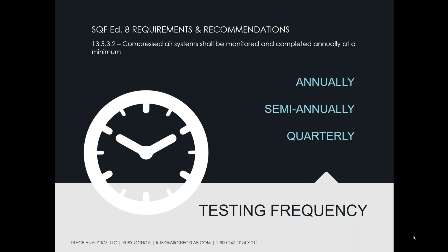What I would recommend is spread them out. Do it for a sufficient amount of time where you have data — where you know that yes, before my filter change everything's working, and yes, after the filter change it's working. Every six months you have enough data to evaluate that your maintenance is working properly and your filters are being changed at the correct frequency. Then you make your decision: based on my results, do I need to change my filters more frequently, or are they doing great? That's the kind of information you can get from a monitoring program.